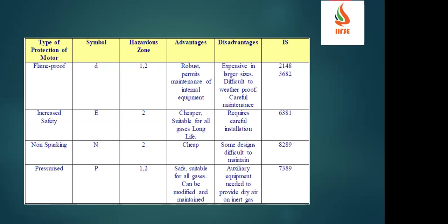because every time there is no chance of presence of hazardous atmospheres. If you see the usage, flame-proof or type D equipments are used in zone 1 and zone 2, increased safety in zone 2, non-sparking in zone 2, and pressurized in zone 1 and 2. Those are the Indian standards you can refer. The advantage of flame-proof is that it is robust and permits maintenance of internal equipment, and increased safety is cheaper, suitable for all the gases, with long life. So wherever there is a leakage of gases involved in your process, or storage of the gas equipments or pipelines, or any storage, there you can use these increased safety electrical equipments. And non-sparking, which is cheap, will be used for working in these atmospheres. And pressurized will be safe, suitable for all the gases, and can be modified and also maintained.